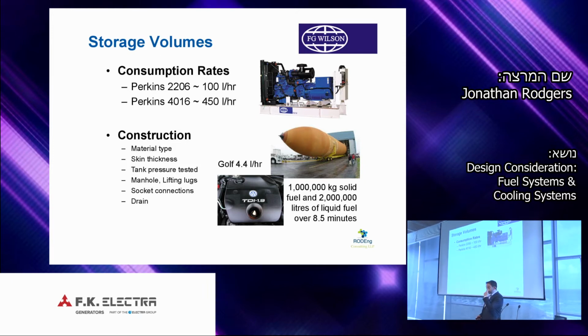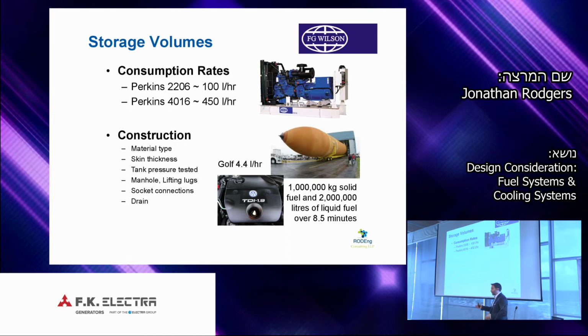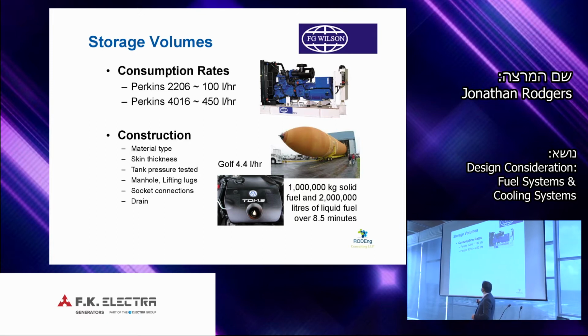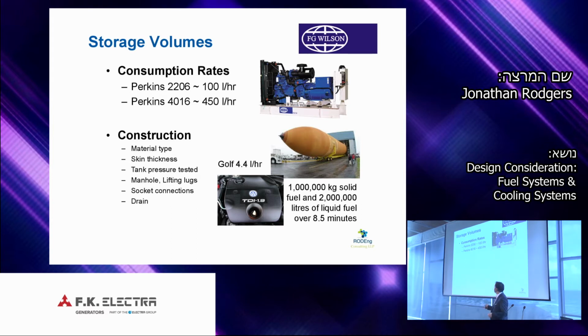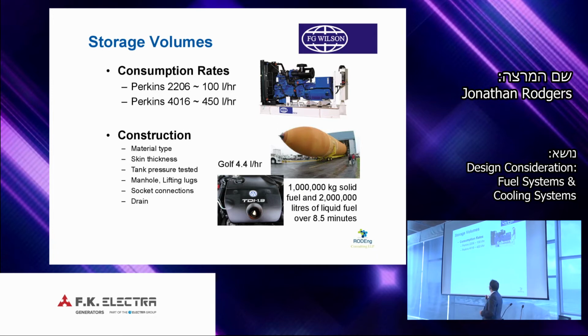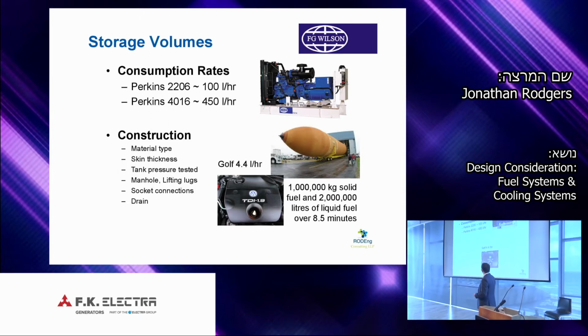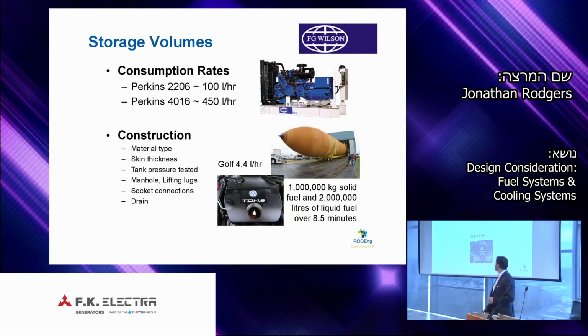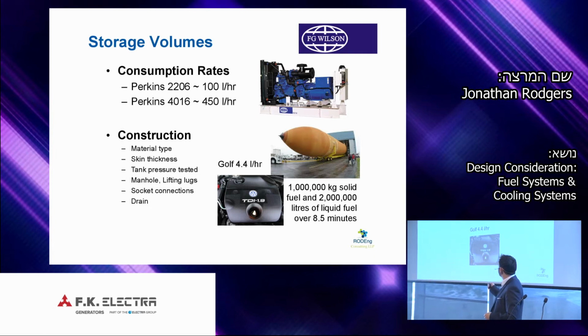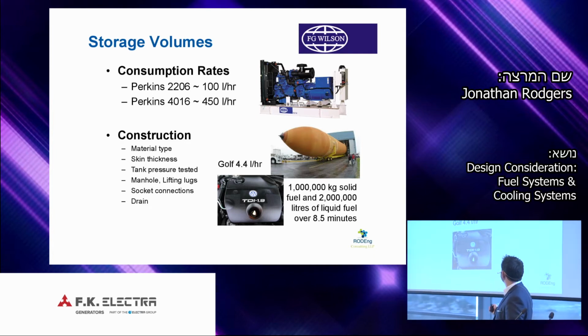So looking at storage volumes, these vary dramatically depending on the size of the engines. So we're looking at how much fuel we're actually consuming and burning. At 2206, 300 kVA, we're talking 100 litres per hour. With 4016, 2200 kVA, 2.2 MVA, we will be using 450 litres per hour. So it's quite a range. If you compare that to the fuel tanks in our cars or motor vehicles, the Volkswagen 1.9 litre engine that is very common uses around 4.4 litres per hour, on average, to give perspective.